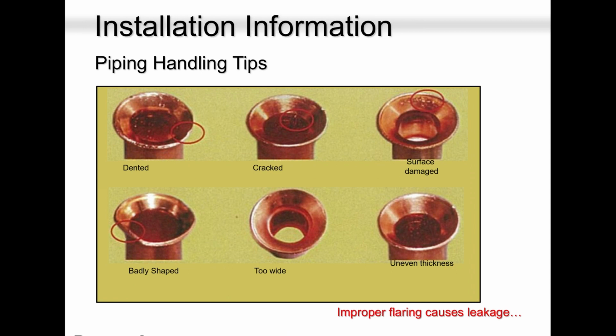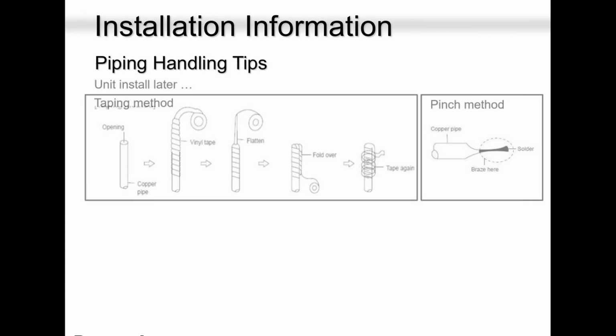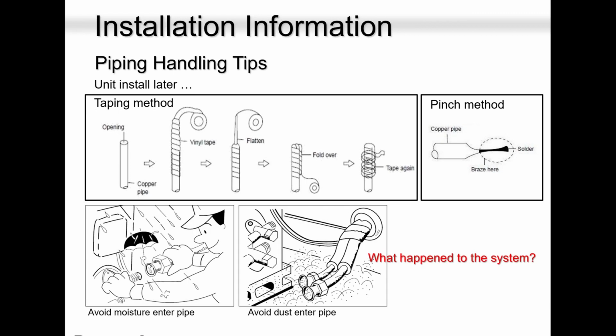Apply a little bit of compressor oil. Go to your nearest supplier, get the compressor oil, the POE, apply to your flaring tool, and you will get a good flare. A lifetime leak-proof flare. Trust me. Everybody knows on a rainy day what happens. 100% humidity. So leaving your pipes open for a longer period of time, or even shorter period of time, you're encouraging trouble. You're encouraging big trouble. So please keep your pipes intact, all the time sealed.